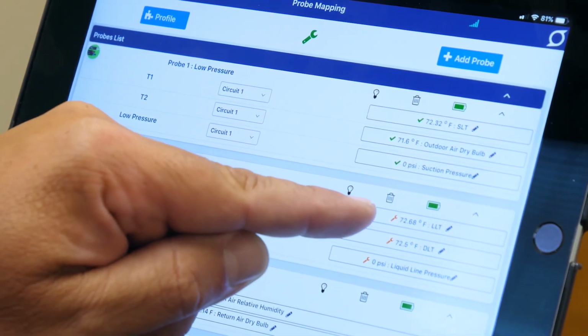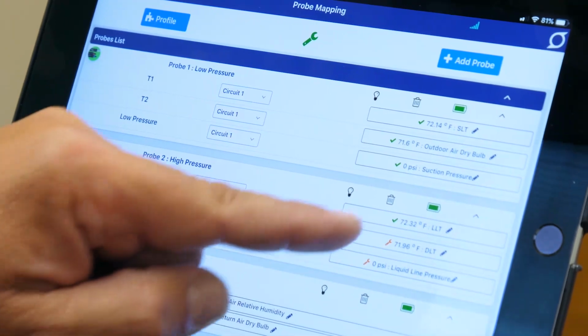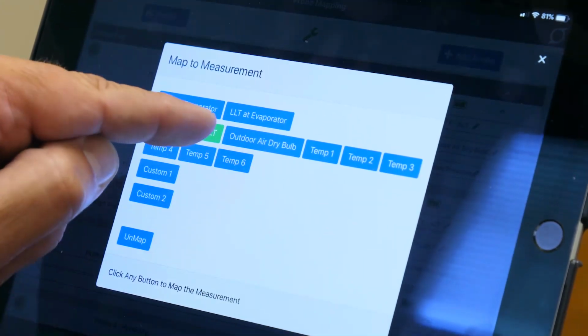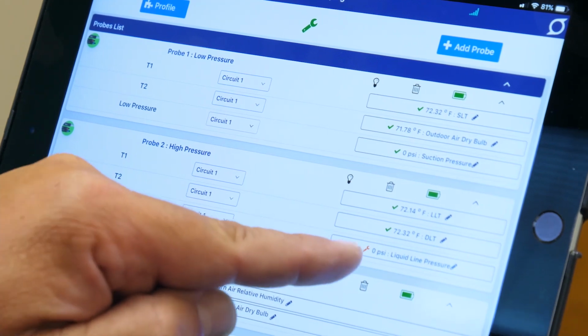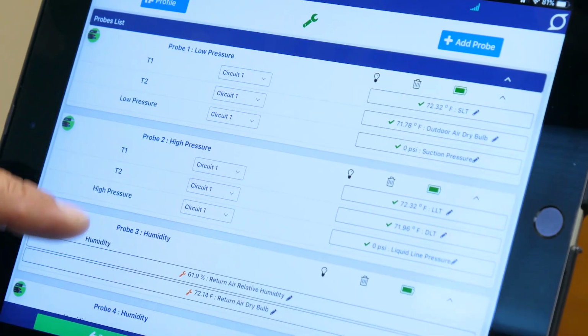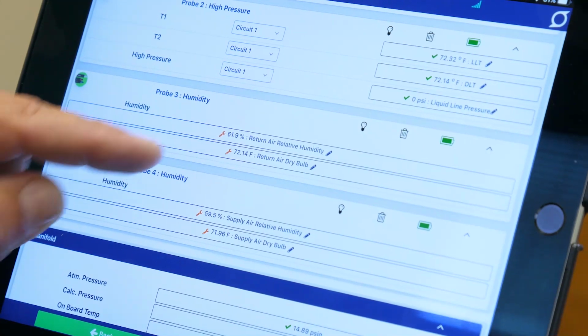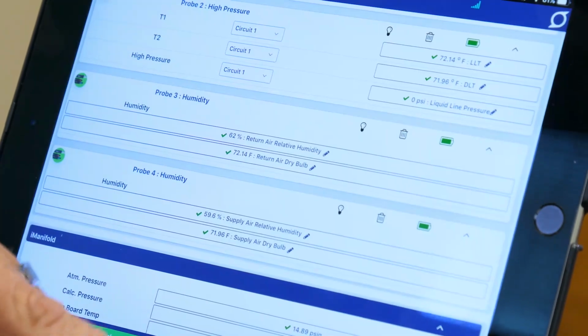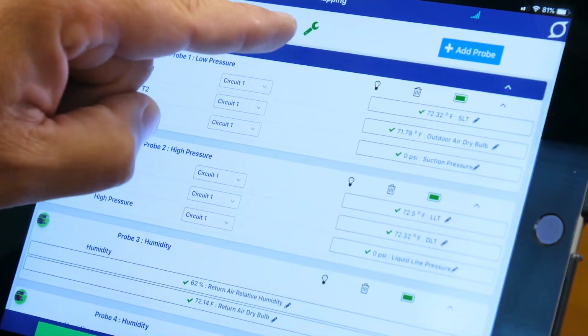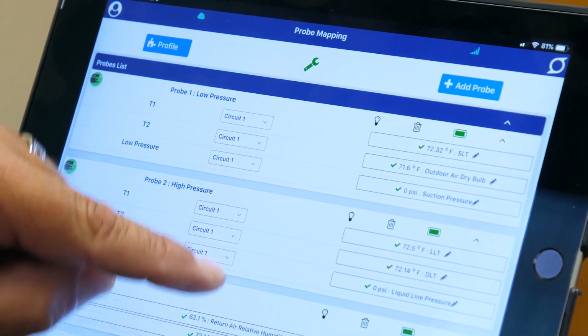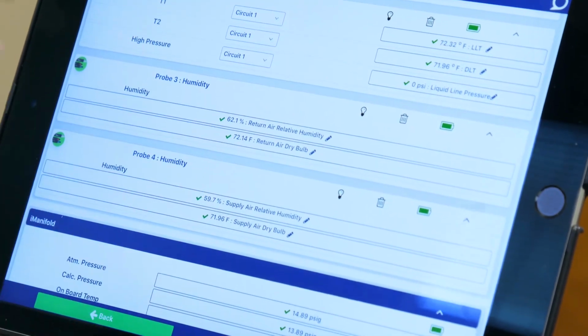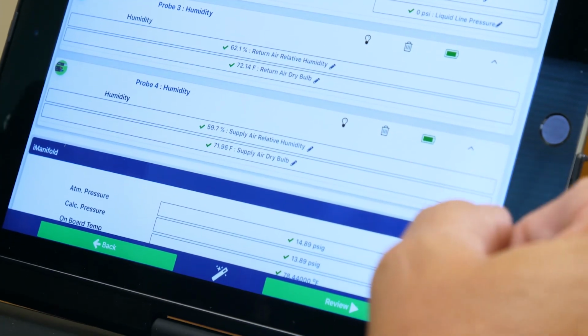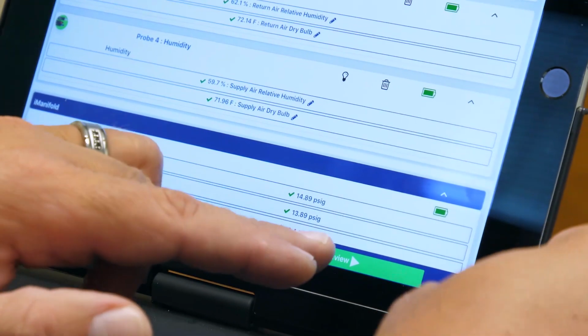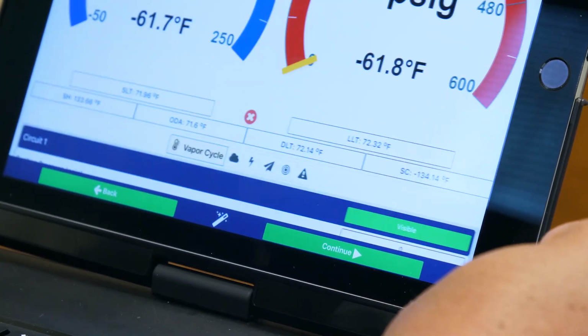Moving to our high side probe, T1, our liquid line temp, just as we discussed. Discharge line temp, we're going to verify that. This is definitely our liquid line pressure side. We just identified these two probes, return air, verifying, and supply, verified. Now, all of our probes are green, everything's check marked. Our wrench is green in the middle here, so we're ready to go. Now at the bottom of the page, we're going to tap review. This is going to permanently pair those probes up with all the values, so you don't have to do this again. So we'll tap review, and now we're ready to work.